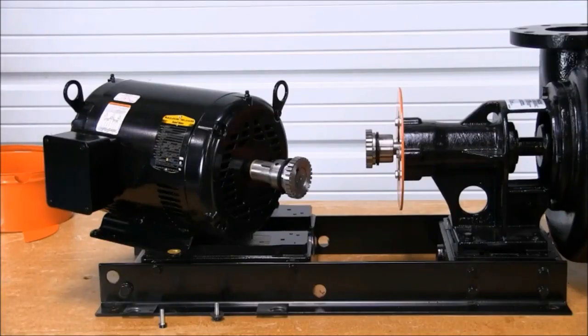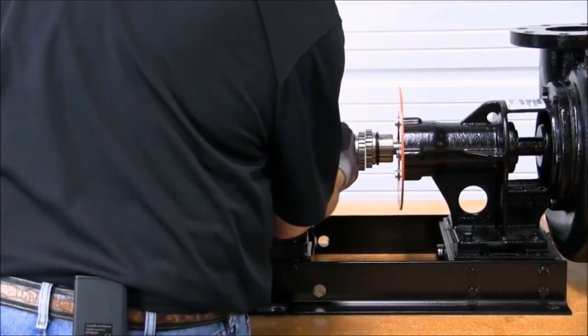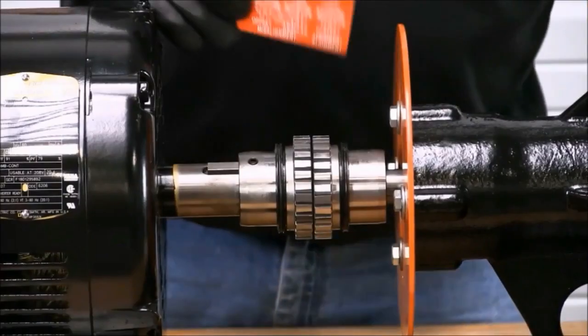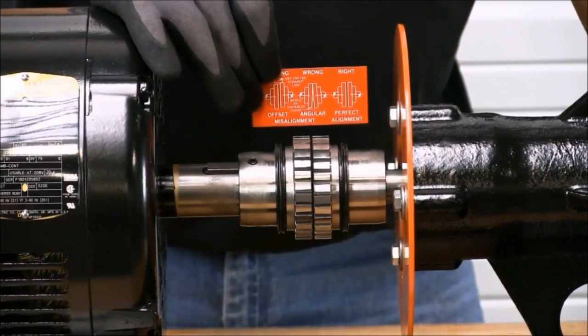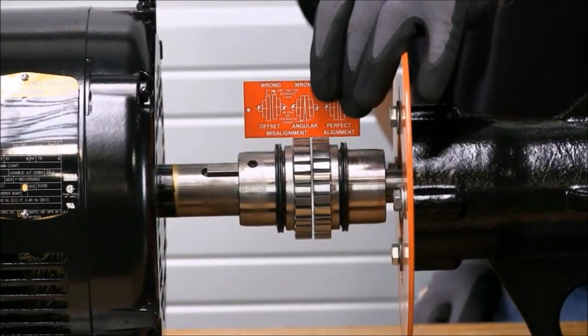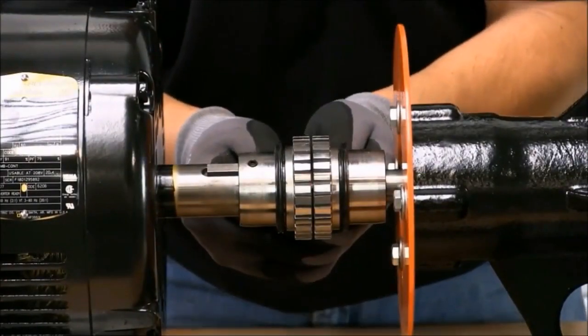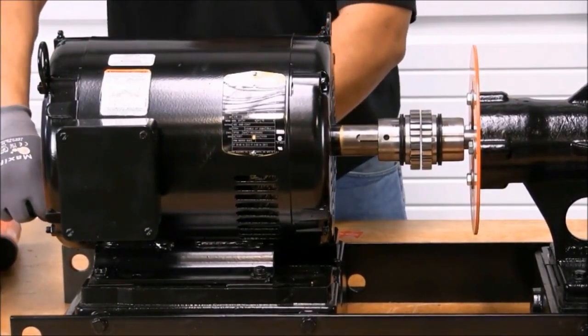Now we're ready to put the motor back in place and perform a pre-alignment. Notice I put all the shims back in their original location for an easier final alignment. Using the straight edge provided with the pump, we're now ready to perform a pre-alignment. First thing we're going to check is the vertical, which is the height. The next thing we check will be the offset, which is side to side. Now that alignment is close, tighten the four bolts using the star-shaped pattern and look for movement and recheck alignment.